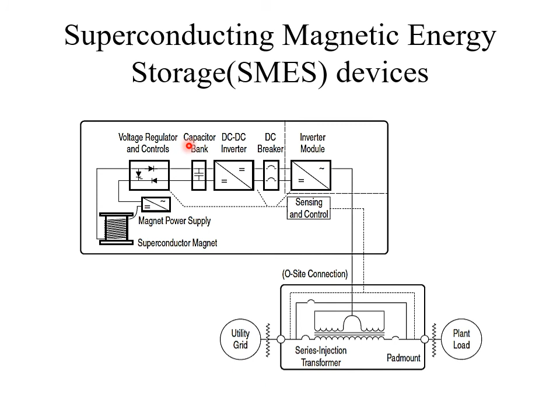The capacitor bank is there to provide voltage to the system, or if there is any overvoltage it can reduce the voltage by absorbing the power. This typical SMES system can protect load up to 8 MVA for voltage sag as low as 0.25 per unit. We know that the voltage sag will be from 0.1 to 0.9 per unit. So even if there is a 0.25 per unit voltage sag, this SMES system can support and provide voltage so that the equipment can operate.